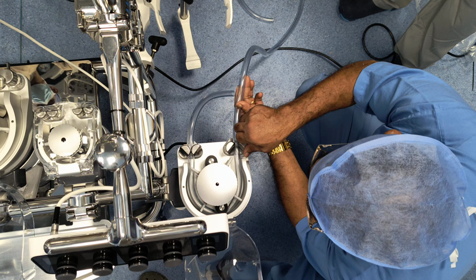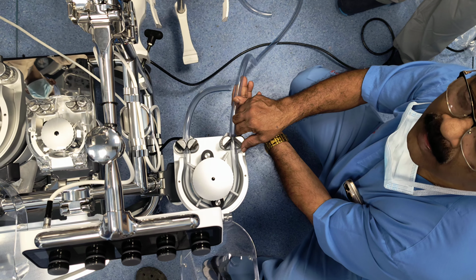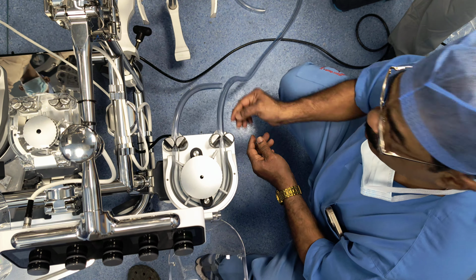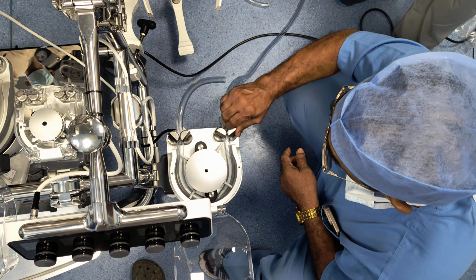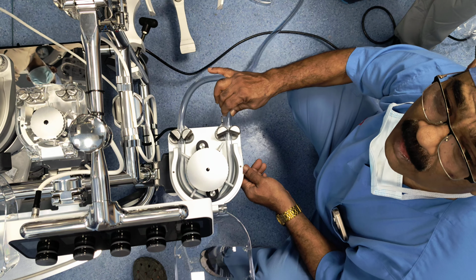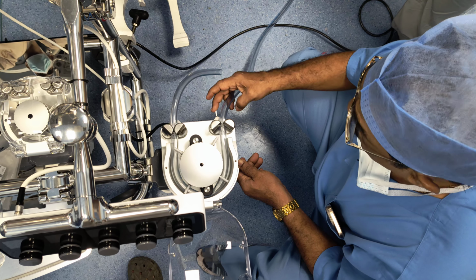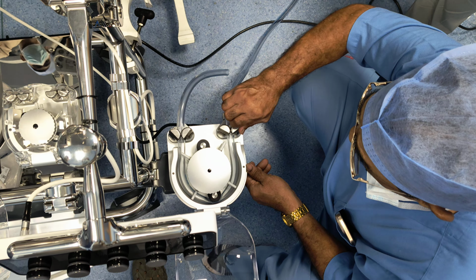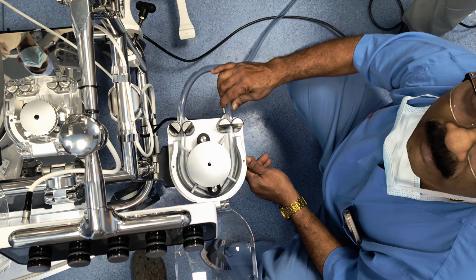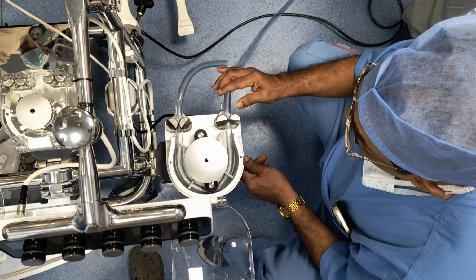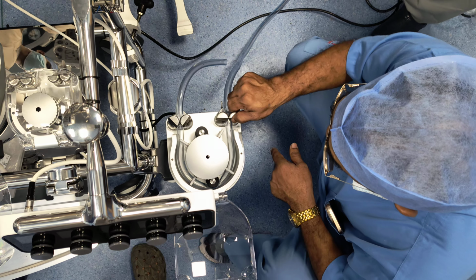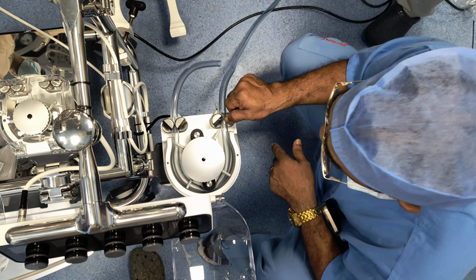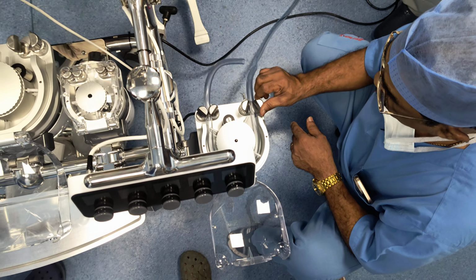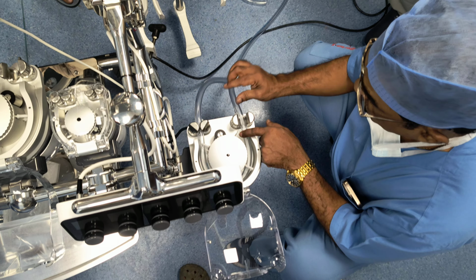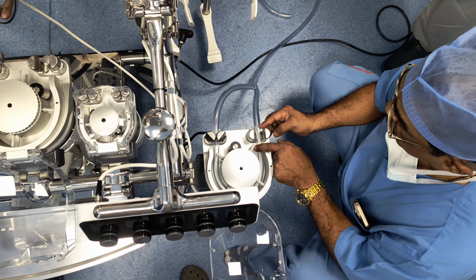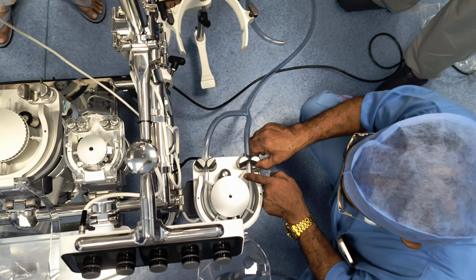Again start turning. What will happen if you do not lock it? It will be loose, no? It will not get locked, yeah. Now the insert, I have kept it open. Yeah. Now, when I tighten it, it's not getting tightened without locking. Yes. Okay. It has gone in, but you see, when the pump moves, there are chances that this will also move. True, true. But it's not totally locking the system without this. Yes, so you have to lock it. Yeah. Okay? And then you keep tightening.